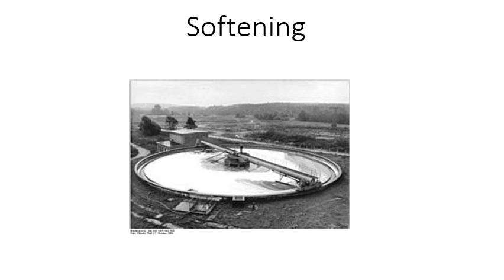You have two types of hardness: temporary and permanent hardness. Temporary hardness is carbonate hardness. So you would have calcium bicarbonate, magnesium bicarbonate. It's easier to remove and not as chemically intensive. Temporary hardness can be removed with lime only. Temporary hardness again is in the form of calcium and magnesium bonding with either bicarbonate or carbonate.